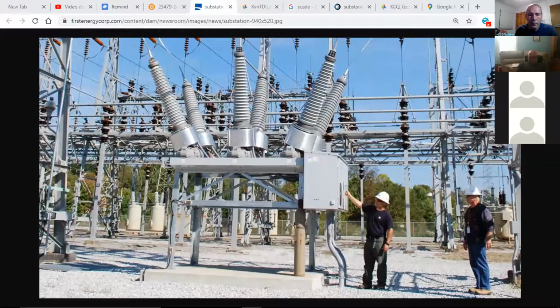Got it. Okay. So I've got a transmission breaker here. Single conductor in, so we'll typically say right around 900 amps. 900 amps in, 900 amps out. I can't take 900 amps in my control panel right here and be able to meter or measure it. It's just way too high. So what am I using to convert that 900 amps down to something that's usable in electronics? The metering current transformer. Current transformer.